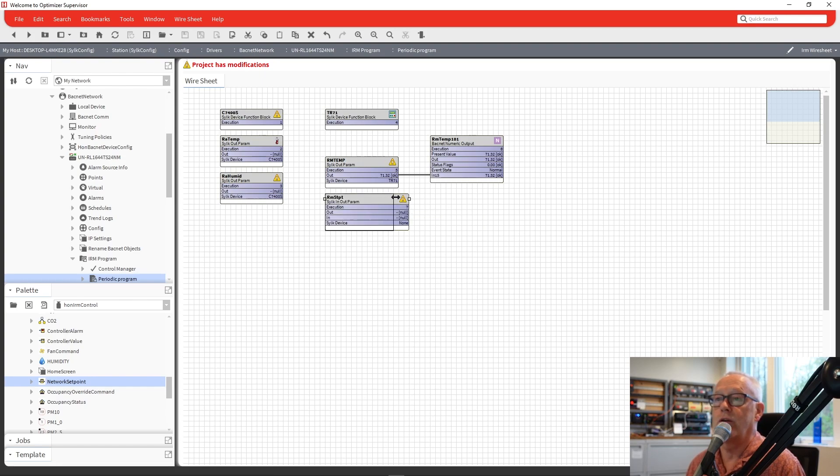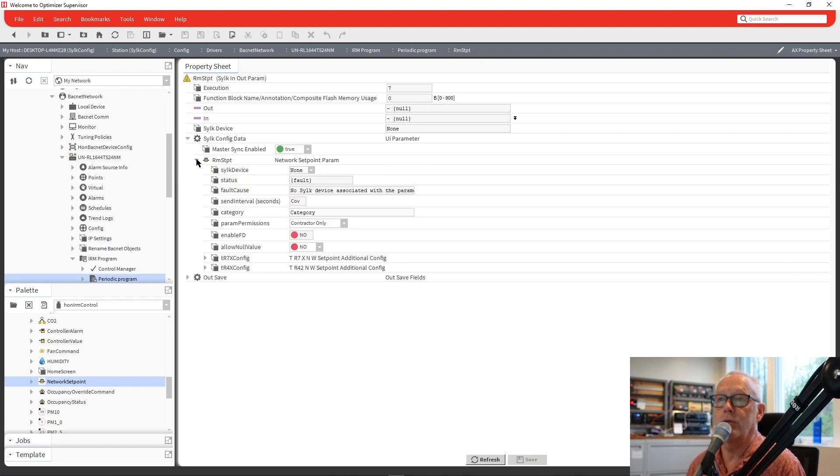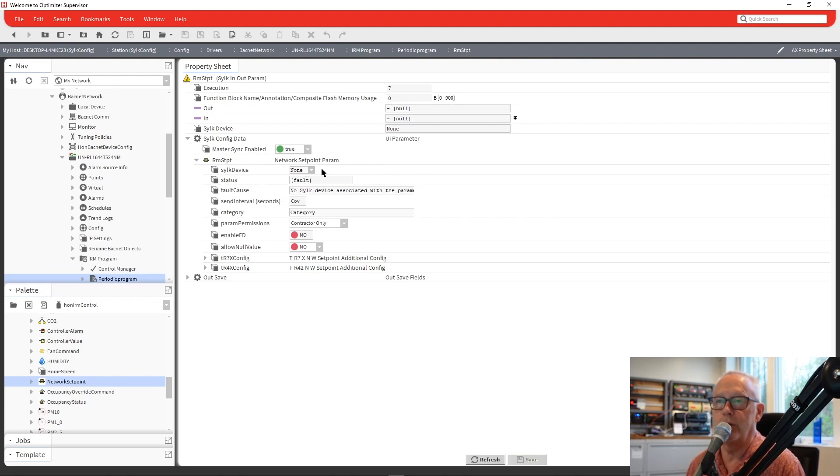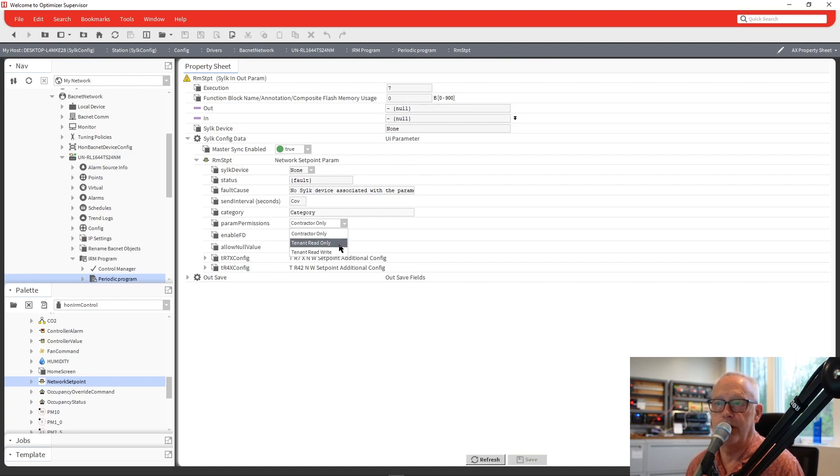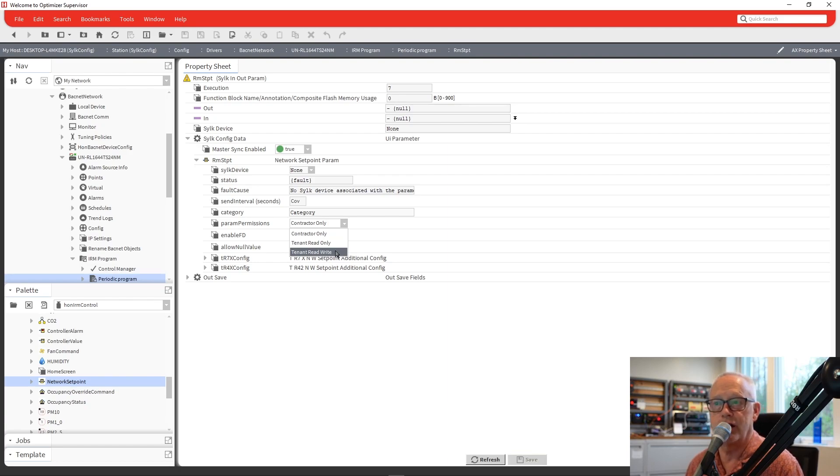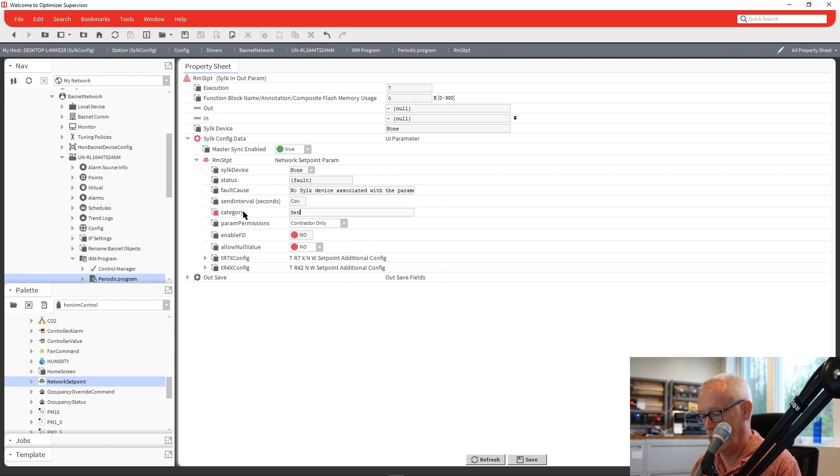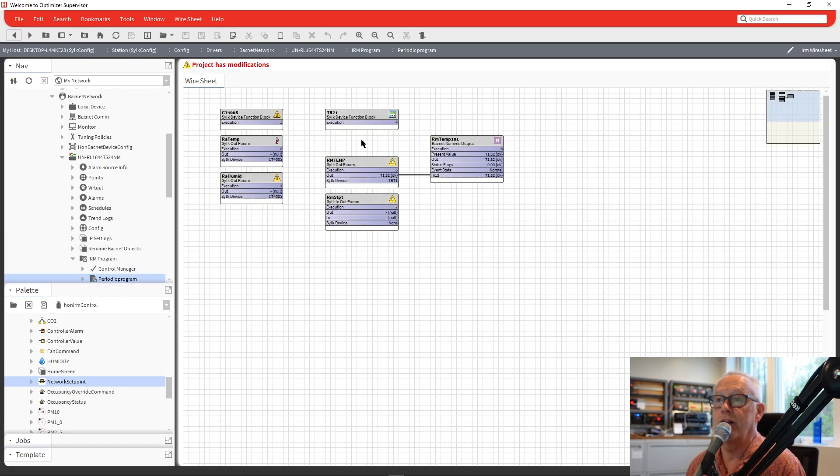So we've got that parameter in here. We can go in and look at its properties. And if we go through there, we'll see we didn't assign a device yet. I'm going to leave that blank just to show you another way to assign all of the devices to the parameters. But we could choose contractor only, tenant read only, tenant read write. So a tenant can have the ability to write it or not or have to go to contractor mode. And the categories we'll do is we'll just put in set point and enter. And then we come back out of there.